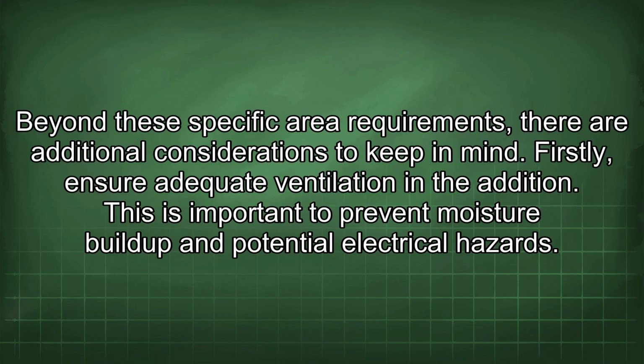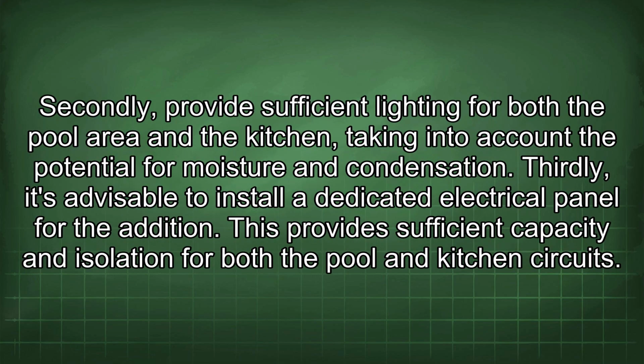Beyond these specific area requirements, there are additional considerations to keep in mind. Firstly, ensure adequate ventilation in the addition. This is important to prevent moisture buildup and potential electrical hazards. Secondly, provide sufficient lighting for both the pool area and the kitchen, taking into account potential for moisture and condensation. Thirdly, it's advisable to install a dedicated electrical panel for the addition. This provides sufficient capacity and isolation for both the pool and kitchen circuits.